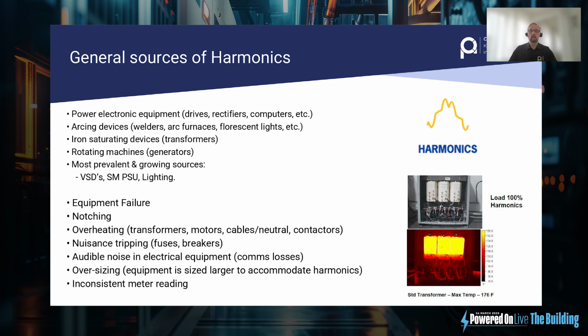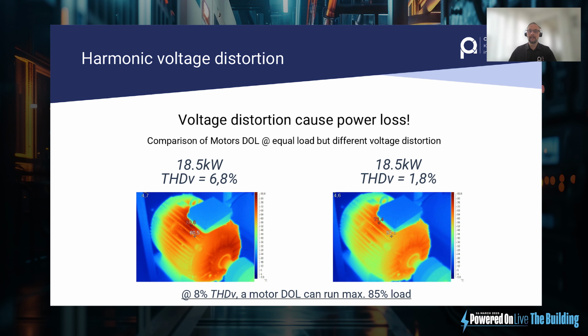And a lot of things we mentioned before, there's other things that can cause issues with regards to the transformers overheating, which is your supply basically to your EV chargers and everything else that might be on that same network. In addition to that, what gets overlooked is if there is a voltage distortion created by these devices that are taking this nonlinear current, then that transformer will give out a signal to other devices like motors that 8% voltage distortion could reduce their torque output by 15%. So there's a lot of hidden things that go on if we don't keep our power supply clean and healthy, i.e. healthy power quality.